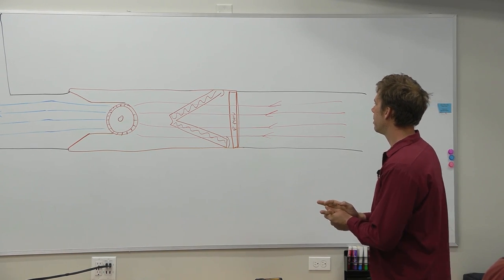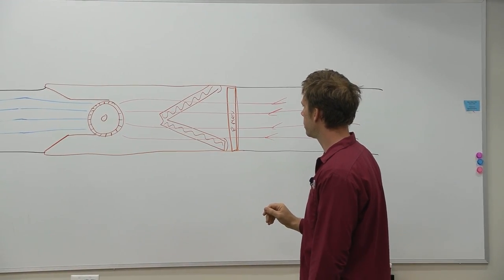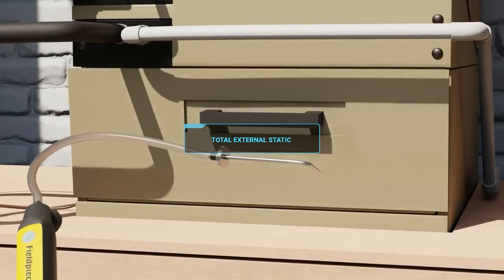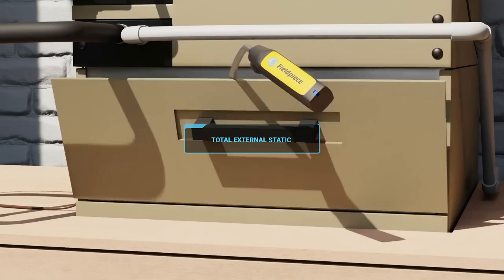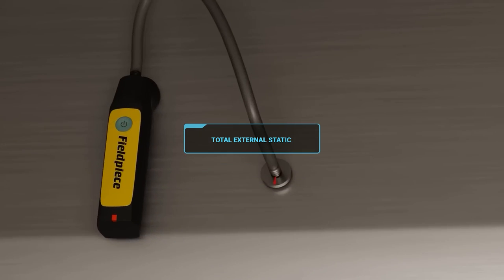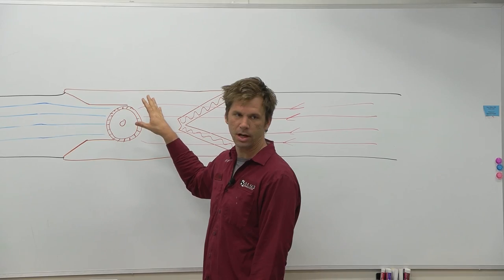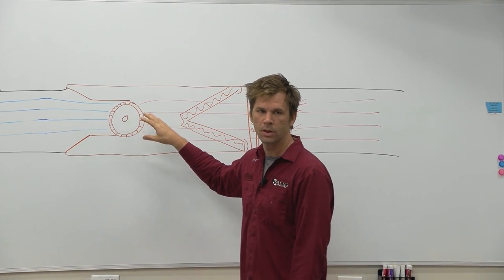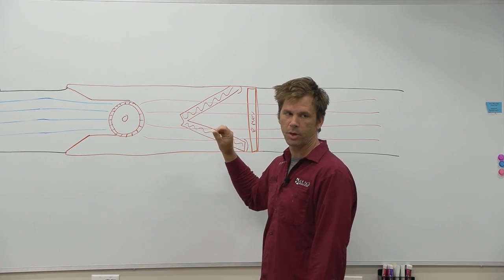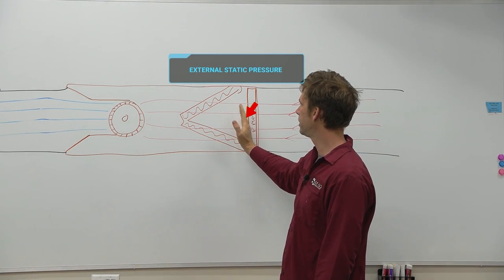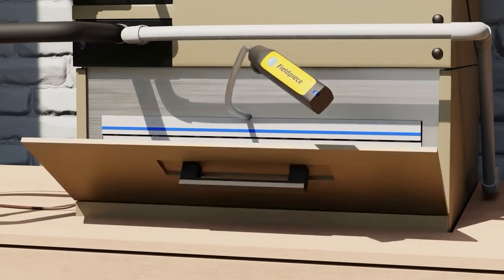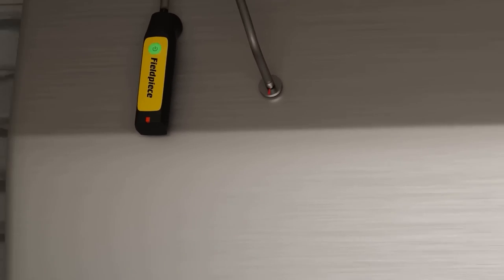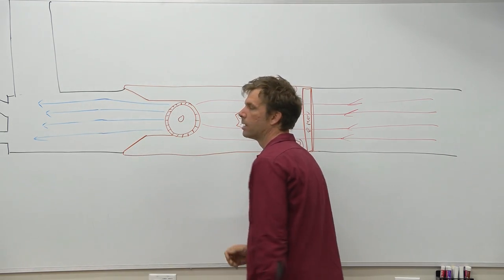As we're measuring our static pressure, we're looking for external system total external static. This is a measurement that is done to find out how well is my unit operating, how much airflow do I actually have, how much resistance is the blower fighting.